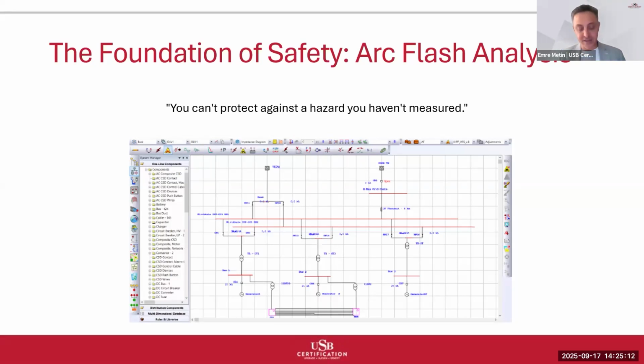Because arc flash hazards vary dramatically within the same facility. The incident energy at a 480 volt motor control center might be 5 cal/cm², while the main electrical room might have areas with 25 cal/cm² or higher. Without analysis, you are making protection decisions blindly.